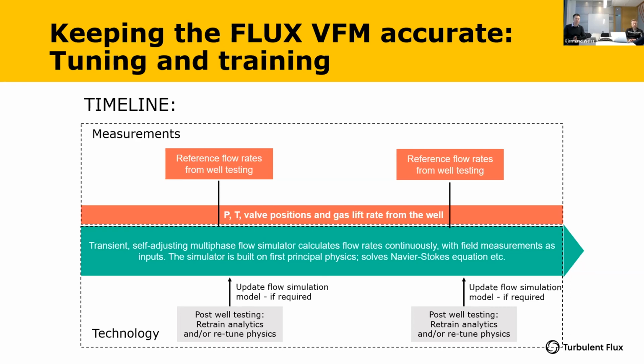So I'm going to talk a bit about how we are keeping the Flux VFM accurate over time. This is a timeline representing the Flux VFM in operation. The transient multi-phase flow simulator calculates flow rates continuously with field pressure and temperature measurements as inputs. It also receives inputs from machine learning or analytics models.